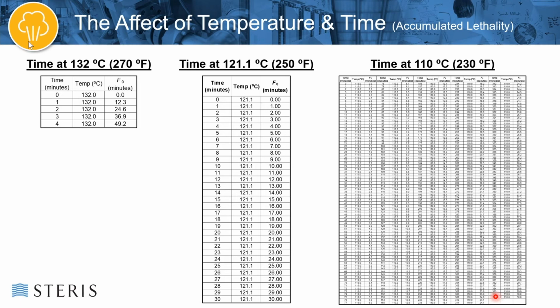So what that means is that at 110 degrees C, you would need to process your load for roughly 6.5 hours in order to achieve the same amount of sterilization activity that you would have achieved at 30 minutes at 121 degrees C. So that's how accumulated lethality works. There's a lot more to it than that, but this is kind of a high level. I just want you to understand what people are talking about when they talk about accumulated lethality or F sub 0.